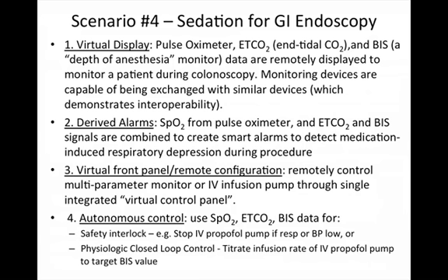Typically, treatment rooms are cramped environments. There are, in this case, gastroenterologists performing the procedure. There are assistants, maybe students, nurses, and members of the anesthesia team. Hard to say. There are many ways in which the procedure is performed, but in general, we're dealing with a cramped environment, and it can be physically difficult to access the infusion pump. Why not make that more convenient? Why not improve workflow in order to allow access and control of the device from a more central location that's closer to the personnel?